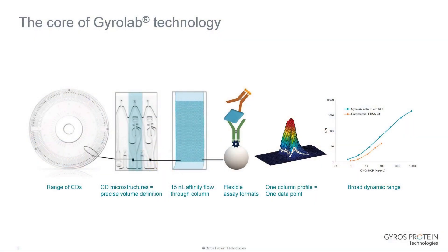The core of the Gyrolab technology involves the CD, or compact disc. This is the equivalent of a microtiter plate where the immunoassay reaction happens. We have various ranges of CD involving different volumes, but among the CDs we have microstructures where the immunoassay happens, involving precise volume definitions. Samples and reagents are transferred to the microstructure as part of the instrument. At the bottom of the microstructure we have a 15 nanolitre affinity flow-through column where the immunoassay reaction happens.